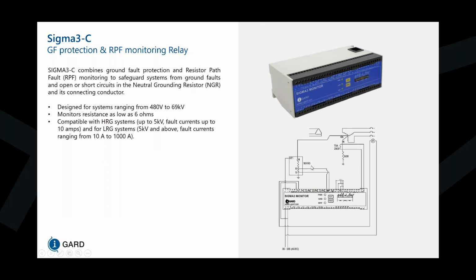Now, because there's a requirement to detect open and short circuit conditions even when there's 0 volts and 0 amps at the neutral, we had to implement an injection method. And that injection method takes the path up through the sensing resistor to the XO point. And once it reaches the XO point, majority of the signal chooses the path through the NGR. We're using a high frequency signal because when our signal reaches the XO point, it'll see these inductances as a higher impedance than the NGR itself, so that majority of our current will flow through the NGR and experience that voltage drop as it comes back to our relay to be analyzed.